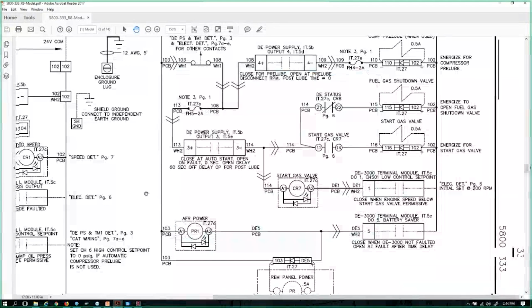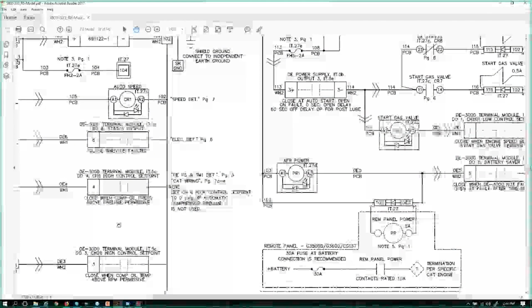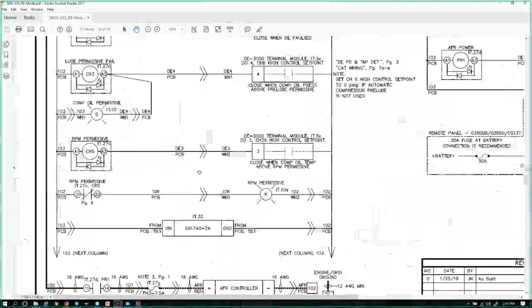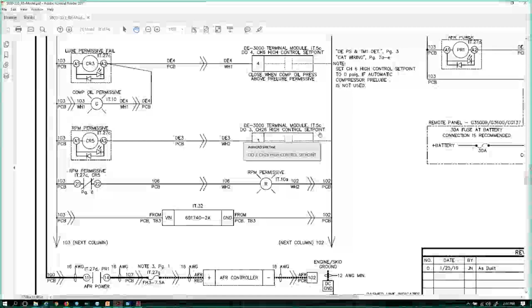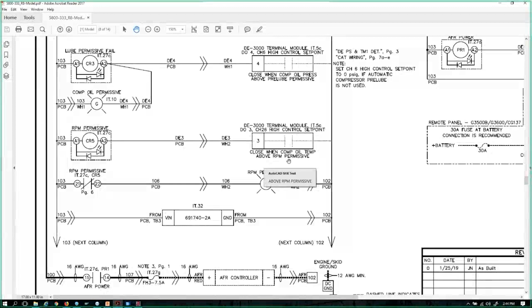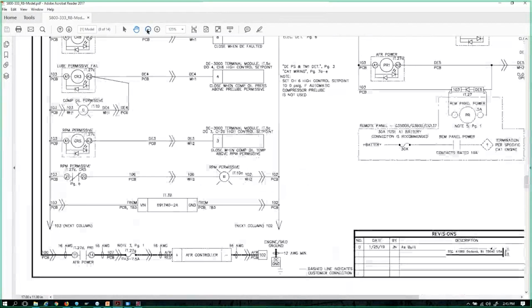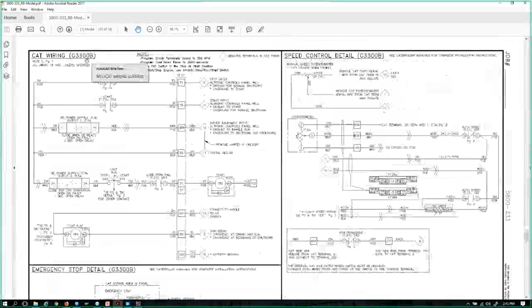In some designs, and I think I have a good example here, RPM permissive. Digital output 3 linked to channel 26, high control set point, closed when compressor oil temperature is above RPM permissive. So I just made that permissive 80. I'm going to close this contact when I'm at 80 and turn on this relay. With one set of contacts from this relay, I'm going to open and turn off a red RPM permissive not satisfied light on the front of the panel. There's a second thing that I do. And I'll see if I can find the engine I referenced a moment ago, which was a 3300B engine.